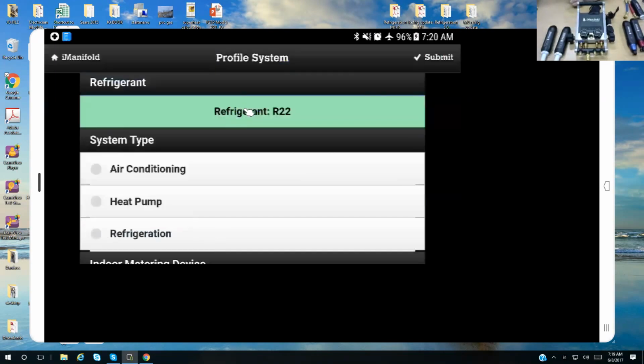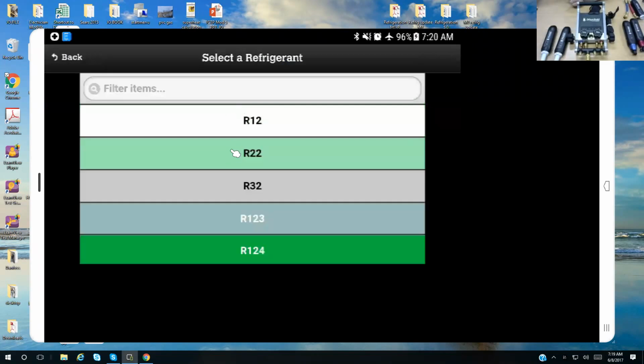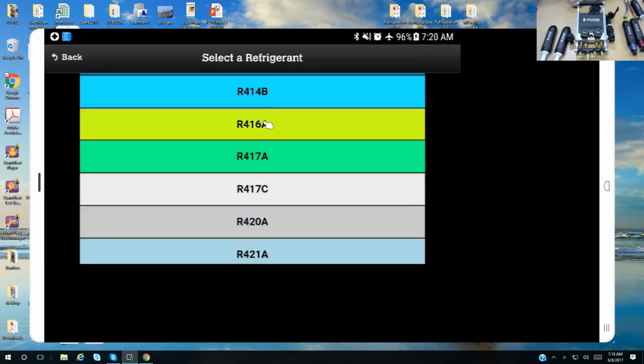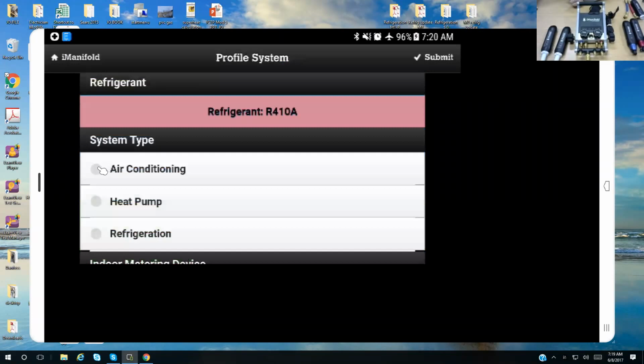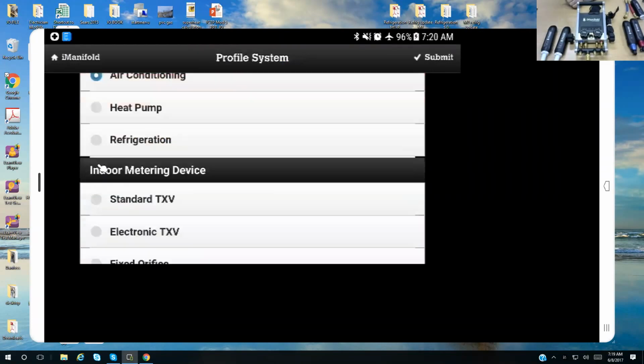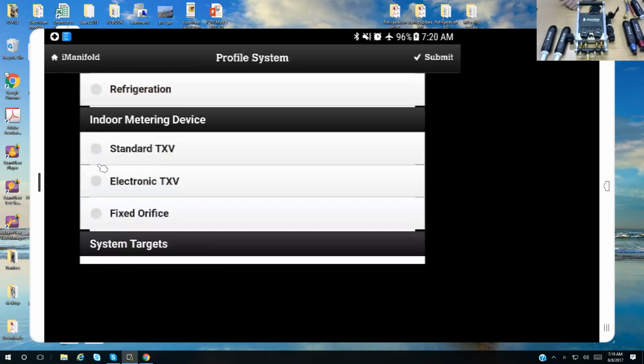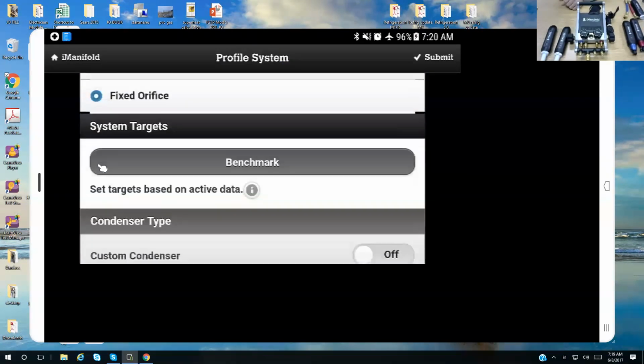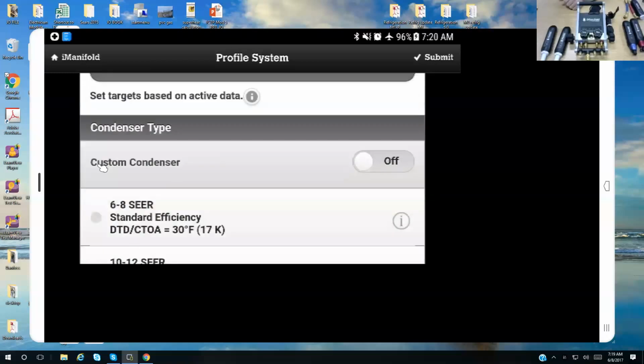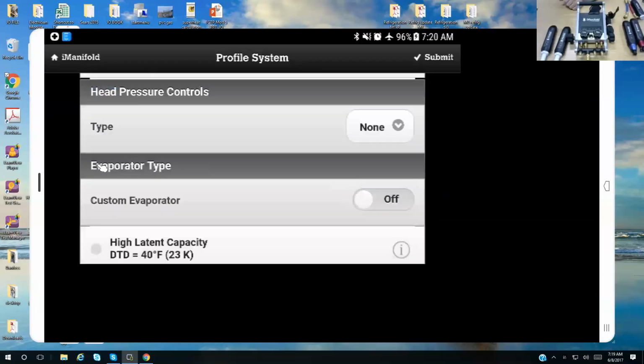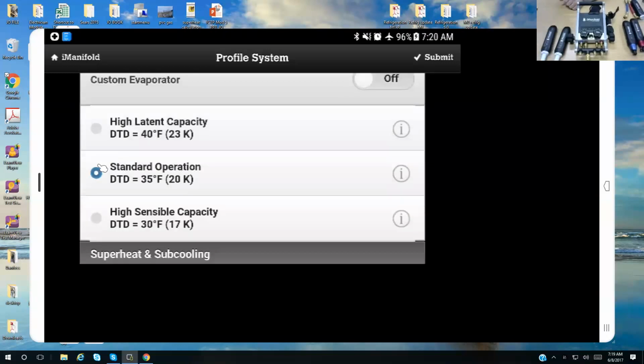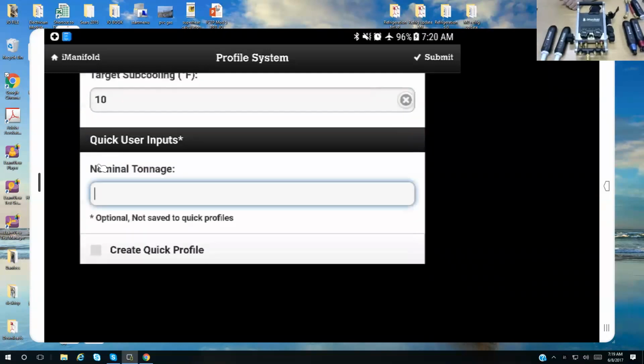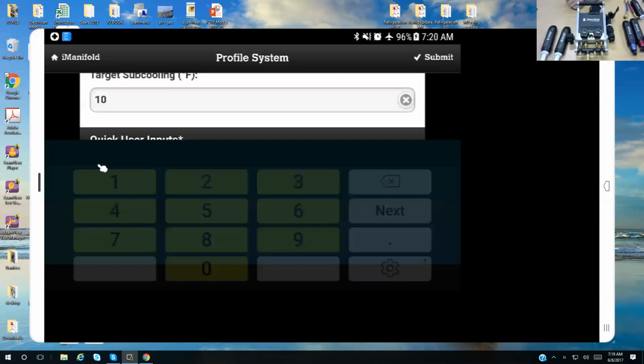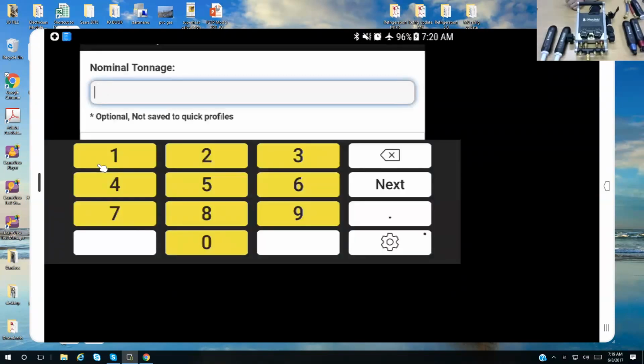If we want to make a new system, we choose refrigerant type. In this case, I'll stick with the R22, or we'll go to 410. Air conditioning system. Let's say it's a fixed orifice. 13 SEER condenser. Standard evaporator. And tons. We don't put in BTUs here. This has got to be tons. So if you have 36,000 BTUs, don't put in 36,000. It's going to try and read that as 36,000 tons. We just put in a 3 for 3 ton.